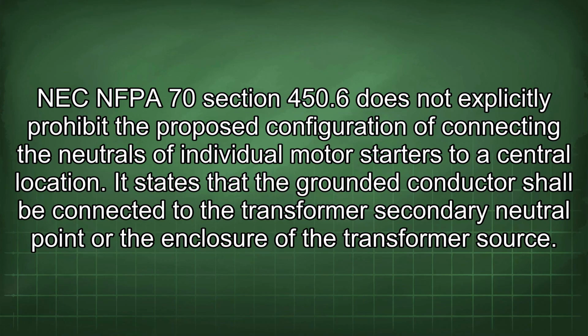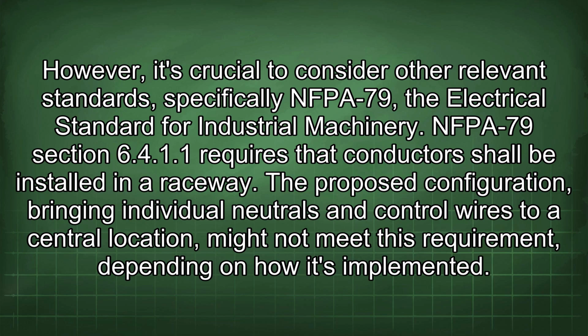NEC NFPA 70 Section 450.6 does not explicitly prohibit the proposed configuration of connecting the neutrals of individual motor starters to a central location. It states that the grounded conductor shall be connected to the transformer secondary neutral point or the enclosure of the transformer source. However, it's crucial to consider other relevant standards, specifically NFPA 79, the electrical standard for industrial machinery.